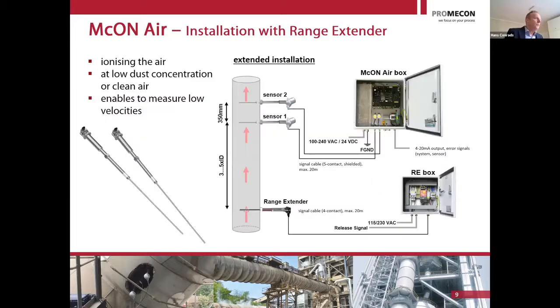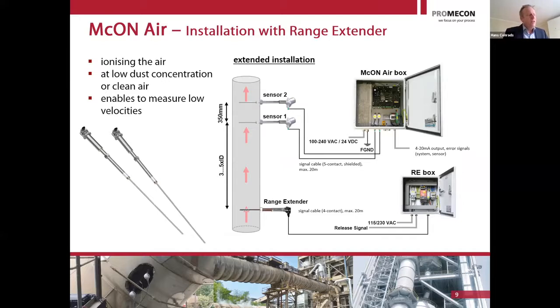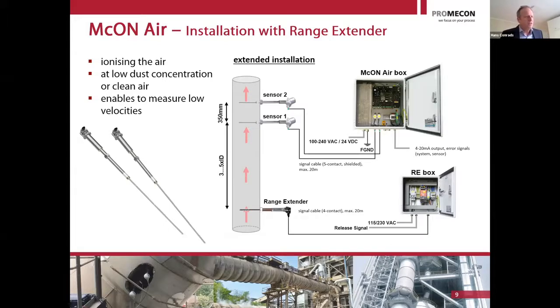We also have a range extender for plants that have no dust present — for example, smelters with a batch process where you sometimes have clean air. An ionizer can give an ionization pulse to the gas and simulate a particle flow, so the measurement can run with and without dust. In cement applications, we don't have anything without dust, so this is really for the power industry and smelter industry — it's a special version of the system.